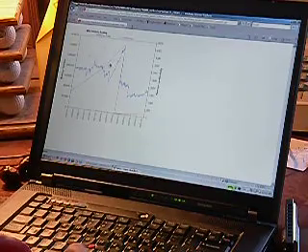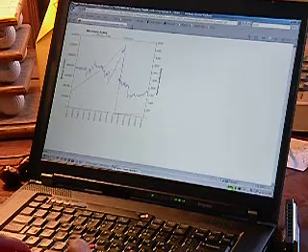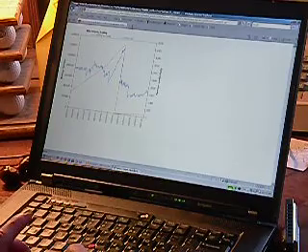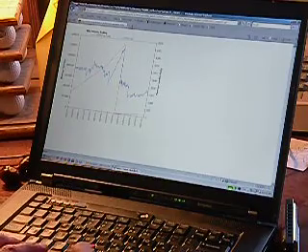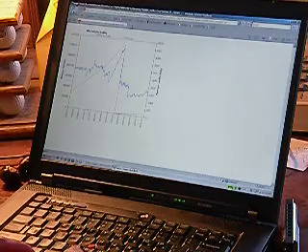So this is the meter reading, and has a big reset here. That's odd. And average conductivity, which is the same as the conductivity line on the last chart we looked at. Well, the same information, the same dates are going on. The conductivity climbed, reached the top, and then it came back down. And so the question is, why did it reset? Well, water meter values only reset because we reset them. So in this case, we hit reset. But this looks like a fairly believable amount.